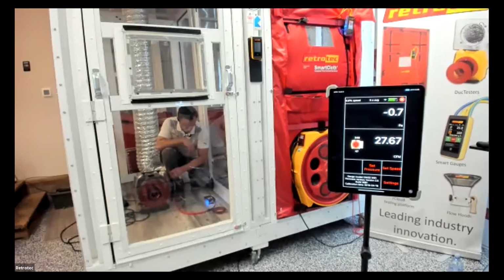And we're getting closer to 0. We still have our flow in CFM. We'll give it a little more juice to see if we can get that 0.4 to go away. There we go. So about 31 CFM total. And if I wanted to go in and change that to CFM per 100 square feet, there we go. So it's going to be a much lower number every time.